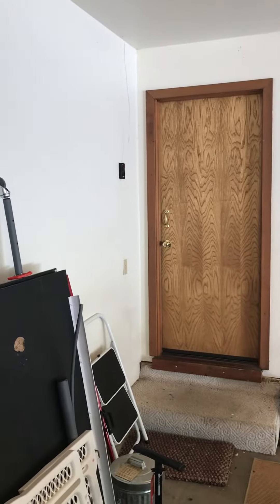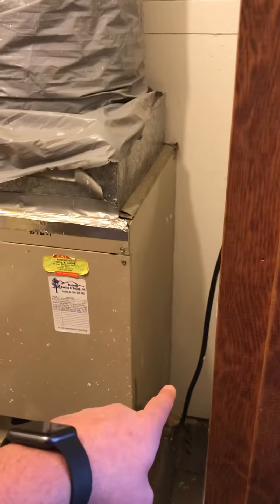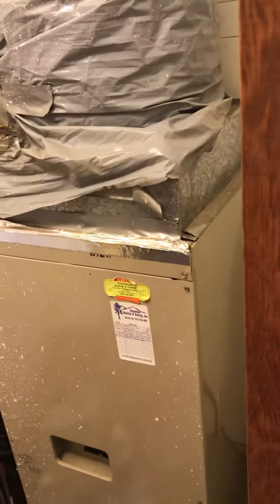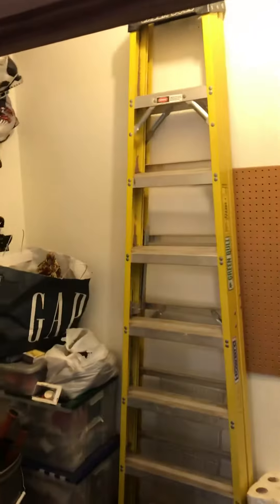The thermostat is just inside the door and it's an old mercury thermostat, so it'll need a new wire pulled. Distance-wise, the crawl starts right here — probably 15 feet to this mechanical room. That's the exterior wall there, so that's where we'd be looking at placement for the heat pump.